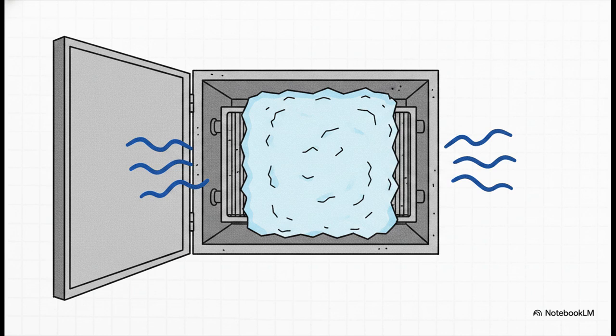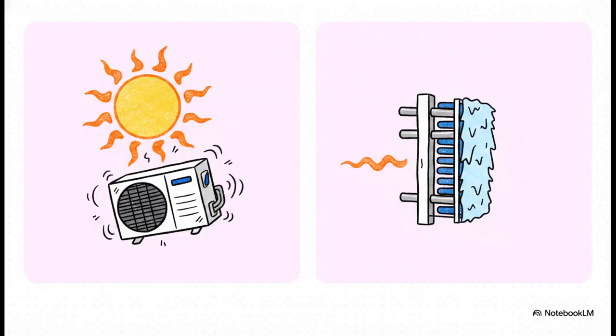This one completely subverts our expectations. You go to open up the air handler, expecting to feel this blast of hot air, and instead, you discover the coil is covered in a literal solid block of ice. No way, right? Now, here is a massive misconception. People see that ice and they immediately assume, oh, the system must be working overtime because it's an absolute scorcher outside. It makes intuitive sense.